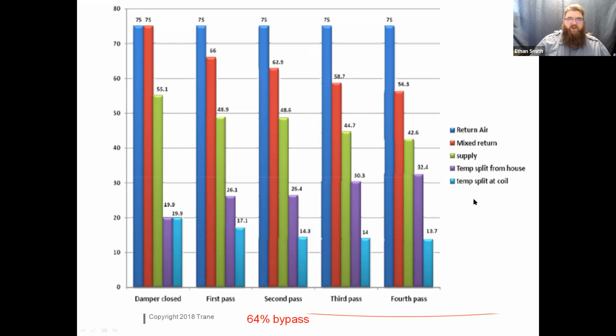So this reduction in coil capacity also translates directly to an efficiency loss. The SEER rating of my equipment is plummeting as my indoor coil capacity goes down. Eventually, this thing's either going to freeze up and go out on a low pressure switch or something like that, or it's going to be cycling on a freeze stat if somebody installed a freeze stat, or a discharge air temperature limit. We'll talk about those when we talk about setup, but this thing's going to cycle off.